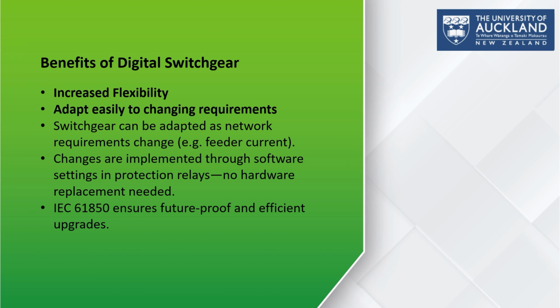Another major benefit of digital switchgear is the increase in flexibility. As network requirements change, such as variation in feeder current, you can easily adapt the switchgear without any physical modification. Most changes can be made just by modifying parameters or logic inside the protection relay. There is no need to replace hardware components, which saves time and cost, right? And because the system is built on the IEC 61850 standard, it remains future-proof, right? So this ensures that any future updates or extensions can be integrated efficiently and seamlessly.